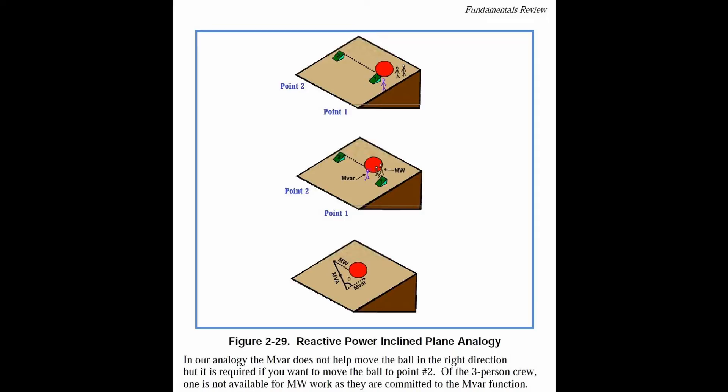That's where a lot of renewables fall short, and solar power is the most glaring example. From a grid perspective, solar just doesn't provide the reactive support needed. For your house, it's great — it becomes a cost ratio question: is it cheaper to buy grid power or put up solar panels and supplement? And if you want to preserve fossil fuels and use renewable resources, that's great at the neighborhood or individual level. But from a national grid perspective, without VAr support, I can't use it as a transmission system operator to move power from generators to distribution.